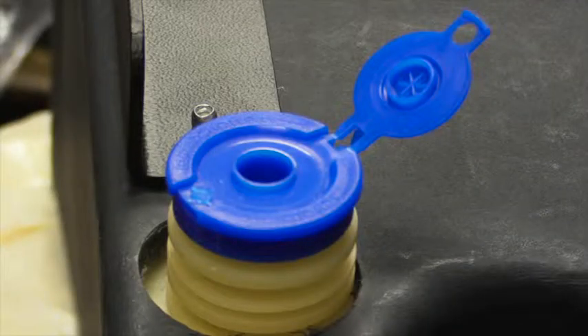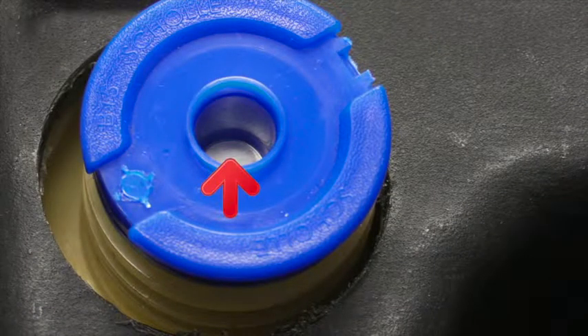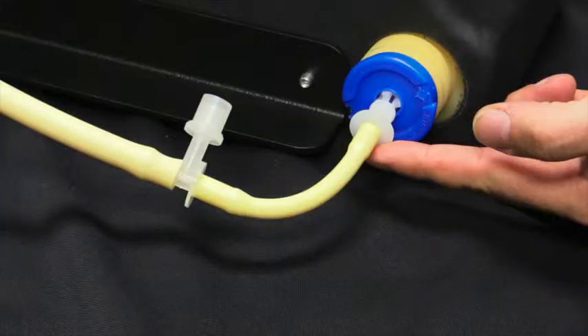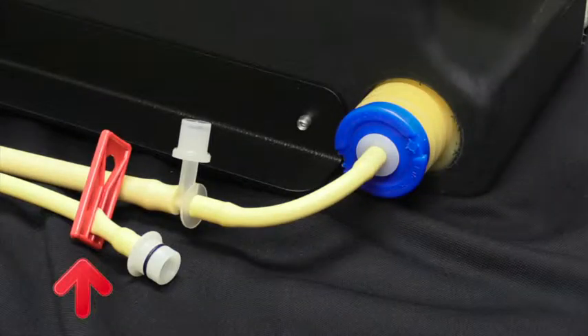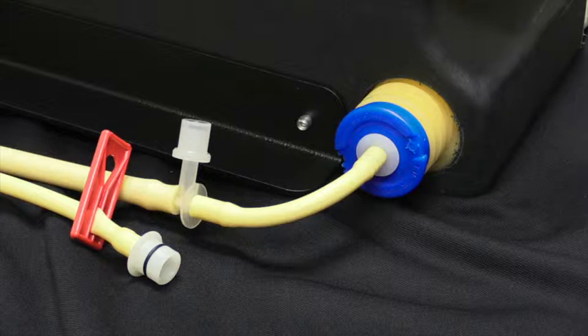Next, we will need to remove the primary plastic cover of the blue cap. Once the safety cap is removed, there is a small foil that will be pierced during the next step of instructions. Next, we will need to pinch off the product hose with the attached red clip. The next step will be inserting the large piercing part of the hose into the blue cap, for which the plastic part that is being inserted into the blue cap assembly will puncture the internal foil, allowing the product to flow into the hose assembly as shown here.